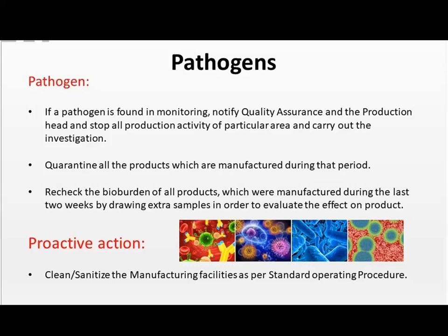All of the products that have been manufactured within that period of when the pathogen was detected are going to be quarantined. They're also then going to recheck for bioburden of all products that have been, again, manufactured within the last 2 weeks, and they may be drawing extra samples.